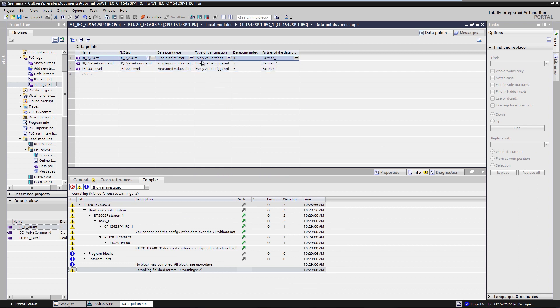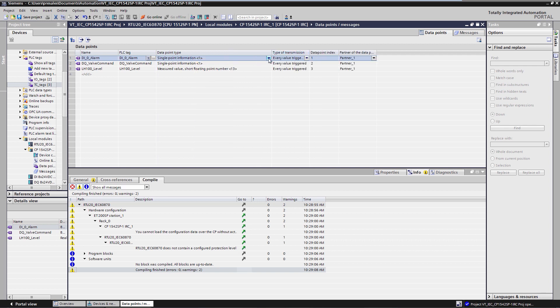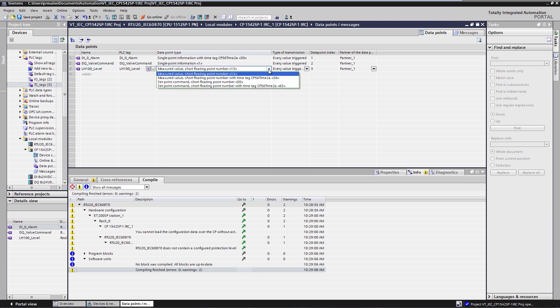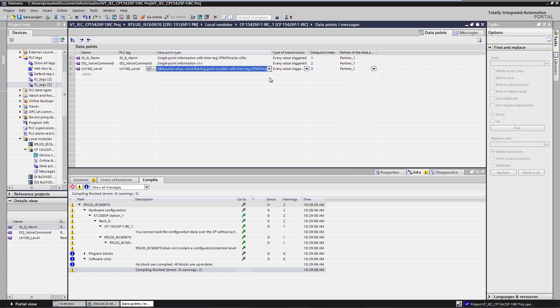I then define the IEC object types and the transmission parameters. According to the task, we send the alarm as single point information to the IEC master, TI equals 30 and IOA address equals 1. According to the task, the measured value of the RTU, i.e. the level of the LH100, is sent as event to the master. Since this is a real value, this is TI 36. Object address IOA is index 3.